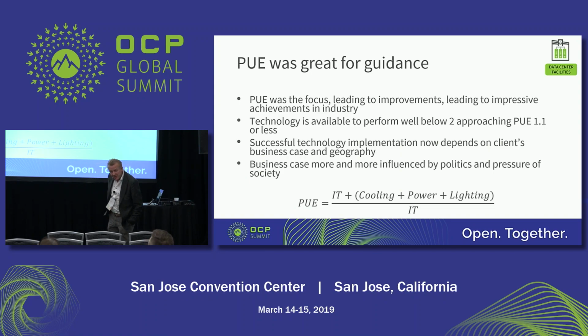When you look at what we did so far, which is quite an achievement when you take into account the time we've been professional in this business, maybe some 20 years, we focused for many years on PUE, and we defined it as a unique quantity already. It has been for many years the measuring point to measure data centers. I would say, and you may disagree or not, that with technology available we can perform well below 2 and close to 1.1, not everywhere, but at many places.